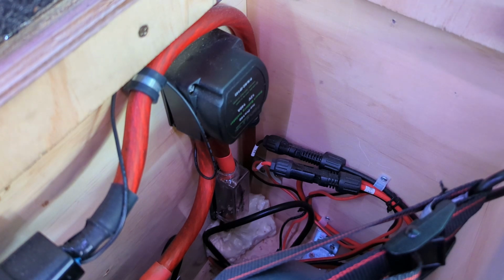To calculate current, you divide the power, 700 watts, by the voltage. Let's call it a nominal 12 volts, though the actual voltage coming from the alternator is 13.99. When you divide that out, it comes to just under 60 amps. I wanted a fuse rated just below that, like 55 amp, but couldn't find one, so I went with 60 amp. It's only 1 amp over the max draw, which should still be safe — in an overcurrent situation the fuse would still go before any significant damage happened. That's why I have a lower rated fuse on this side.